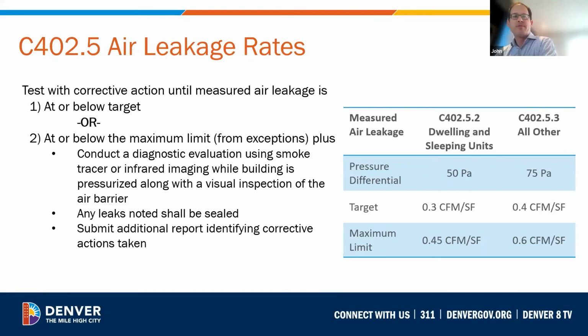Air leakage rates were mentioned briefly before, but this mandatory provision requires continuous air barriers and verification at installation. The air leakage testing has been modified to now require the air leakage to be at or below the CFM per square foot target. So the target for sleeping and dwelling units is 0.3 CFM per square foot, and the dwelling units are tested at a test pressure of 50 pascals, versus the other, non-residential spaces, which are tested at a slightly higher pressure of 75 pascals, and the target level is 0.4 CFM per square foot at the higher test pressure for commercial buildings.